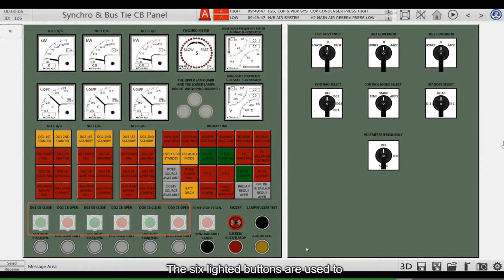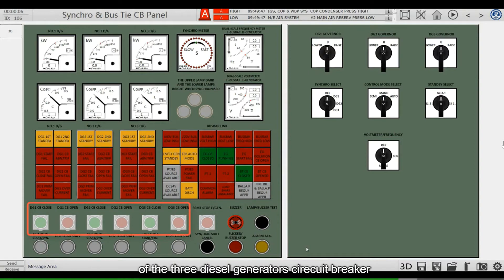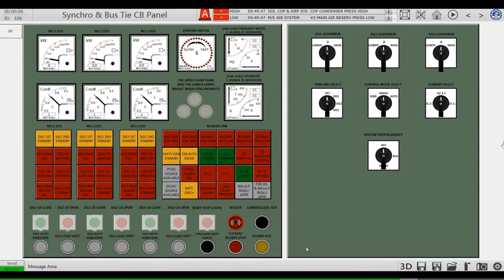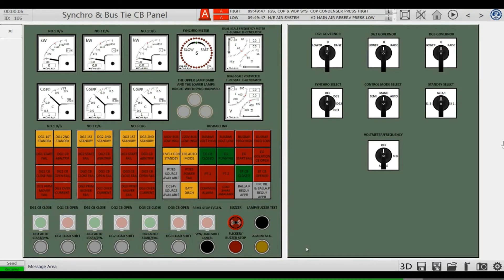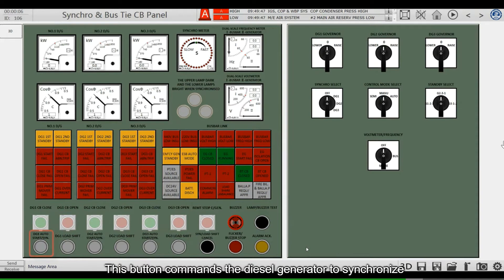The six lighted buttons are used to control the manual closing and opening of the three diesel generator circuit breakers. The following buttons are related to semi-automatic operation. This button commands the diesel generator to synchronize, connect to the grid, distribute the load, and start automatically.